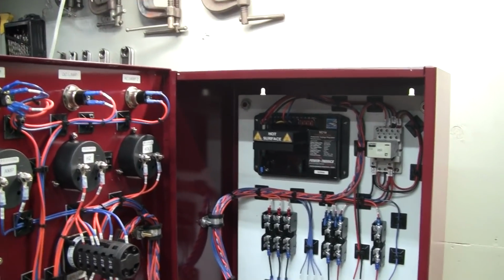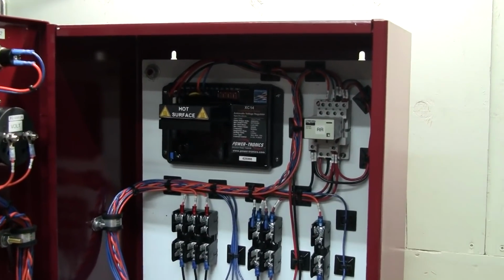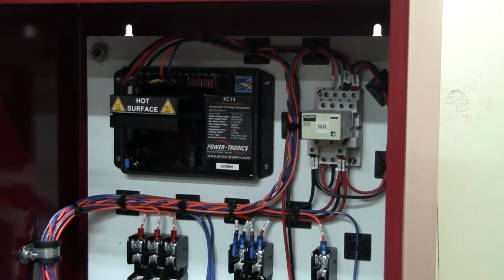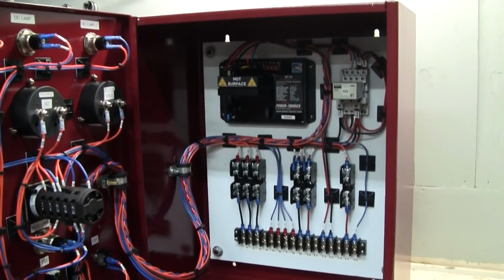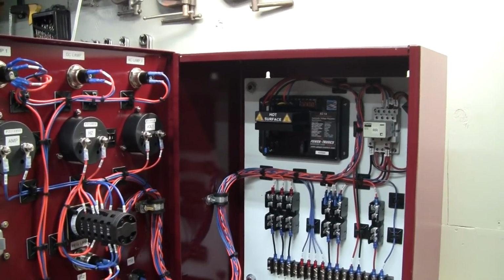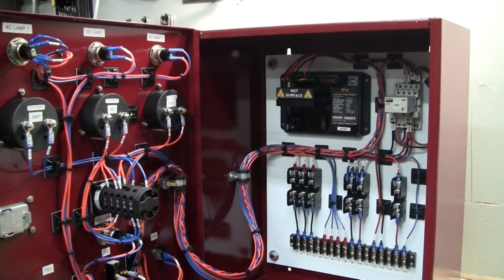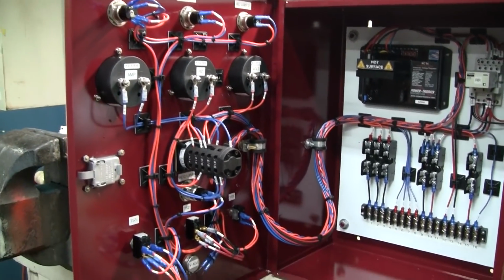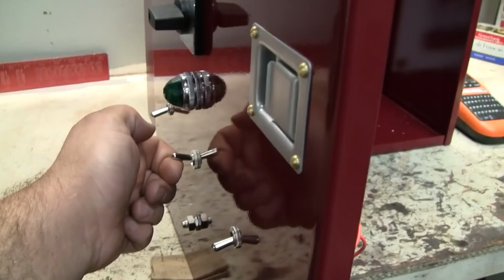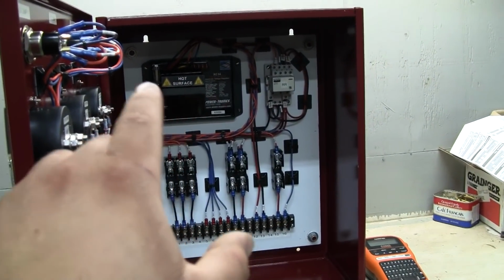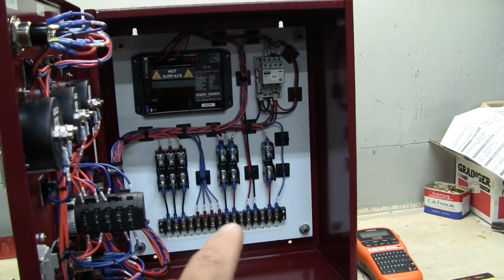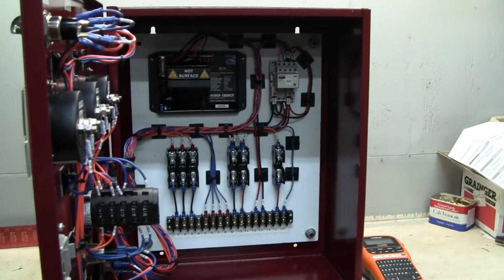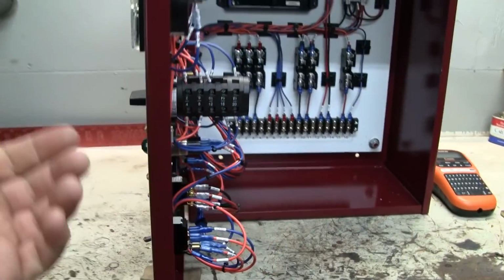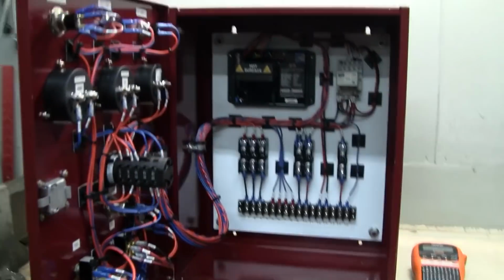So I do not want the regulator to be trying to bring the gen's output up to rated while the engine is running at a low speed, which it may try to do. So just to protect the regulator from trying to force the field of the generator, we'll keep that out of circuit. And then once he switches over to diesel and the thing is up to rated speed, he can lift the toggle, allow generator residual voltage to feed the regulator directly. Once the regulator starts outputting to the field and the generator's output voltage rises to the pickup point of that relay, the relay shunts out the toggle switch, the indicator light lights up, and you can drop out the toggle and we're running. So that's about it here.